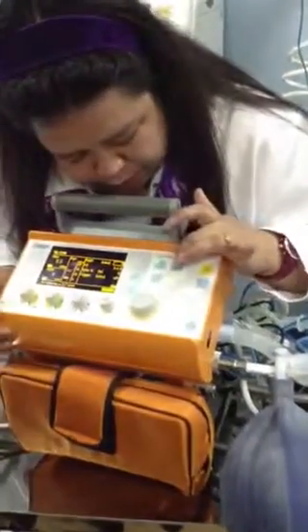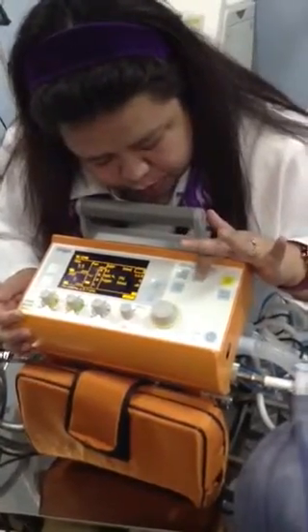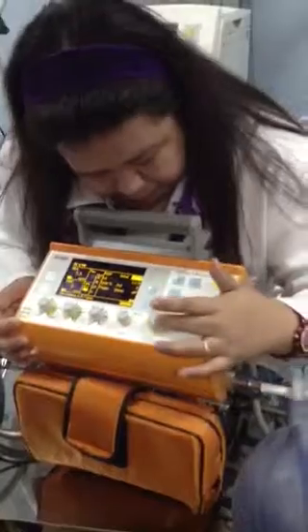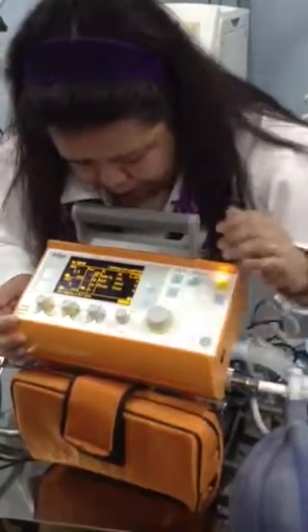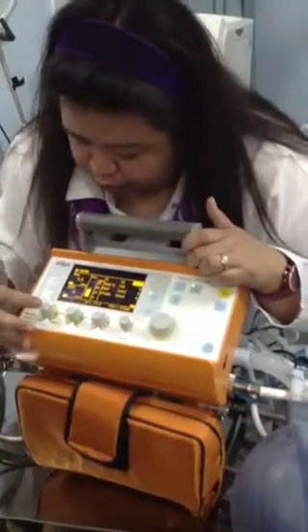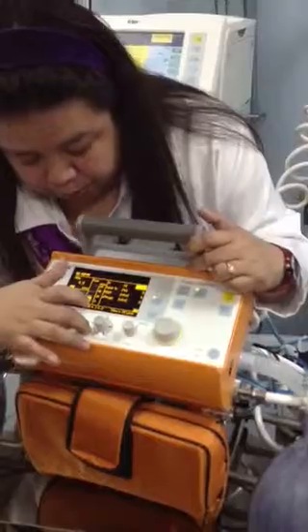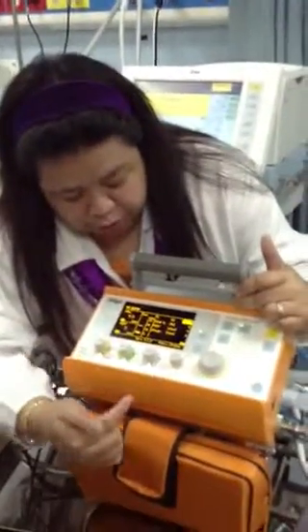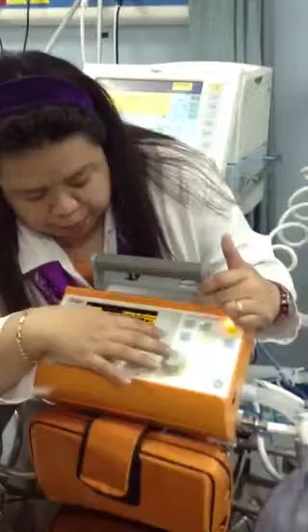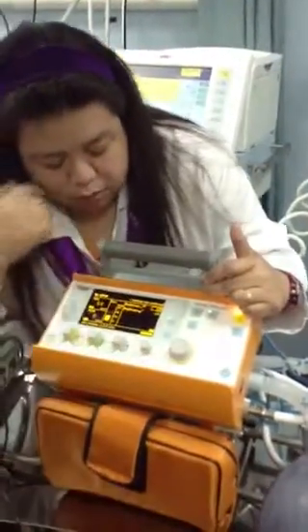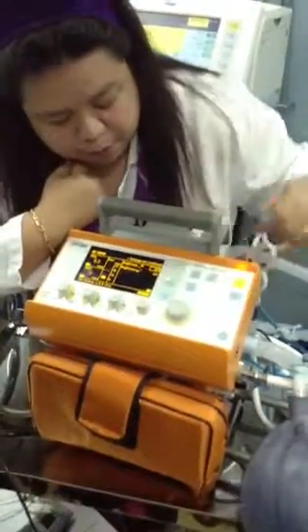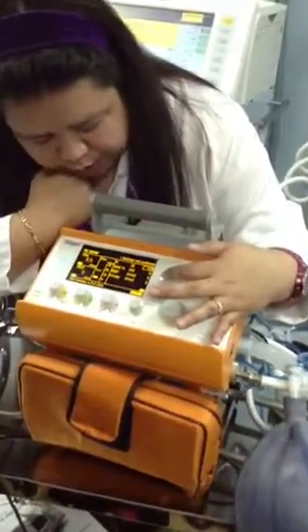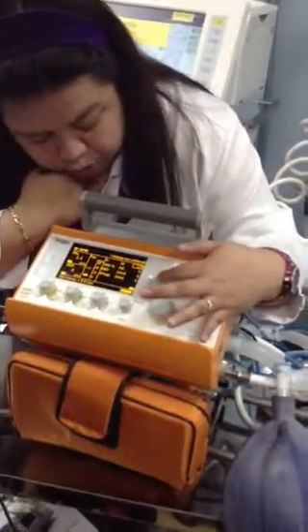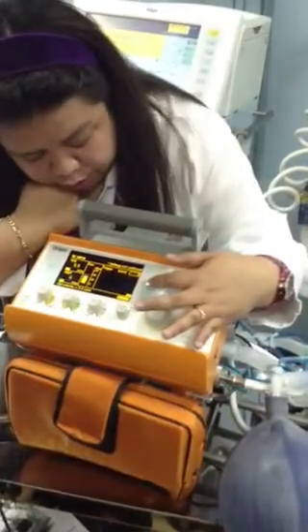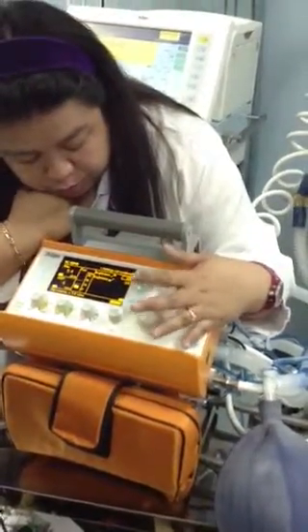Okay. Press this one. Press if you want to choose one setting. Press long. If it starts blinking, press the rotary knob. And press again. This is your tidal volume settings, your RR, and your airway pressure maximum, and your FiO2. Only this one you can set here. But the PEEP and pressure support from your screen. You want to set the PEEP, press settings. There is 3 screen for settings. First one is your inspiratory time and your plateau threshold and your PEEP and your pressure support. This next is your trigger alarm and your brightness, the third screen.